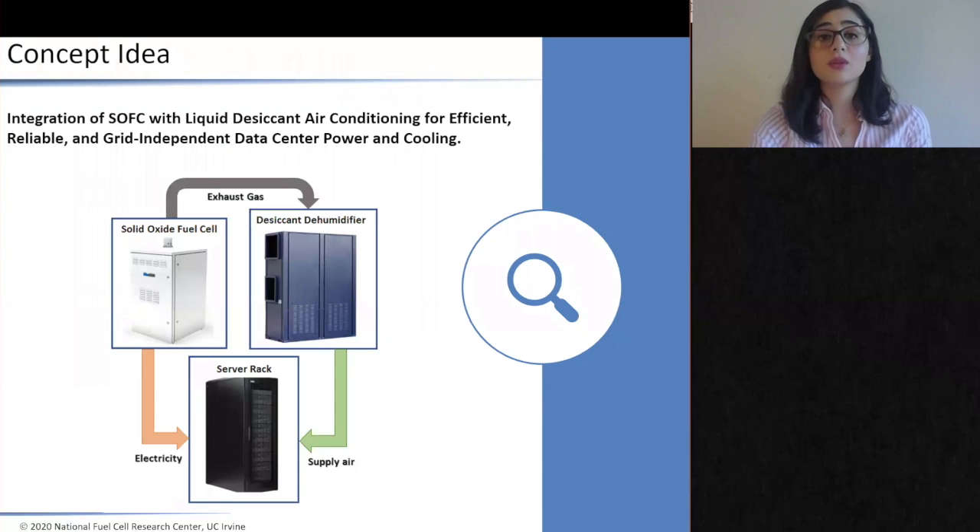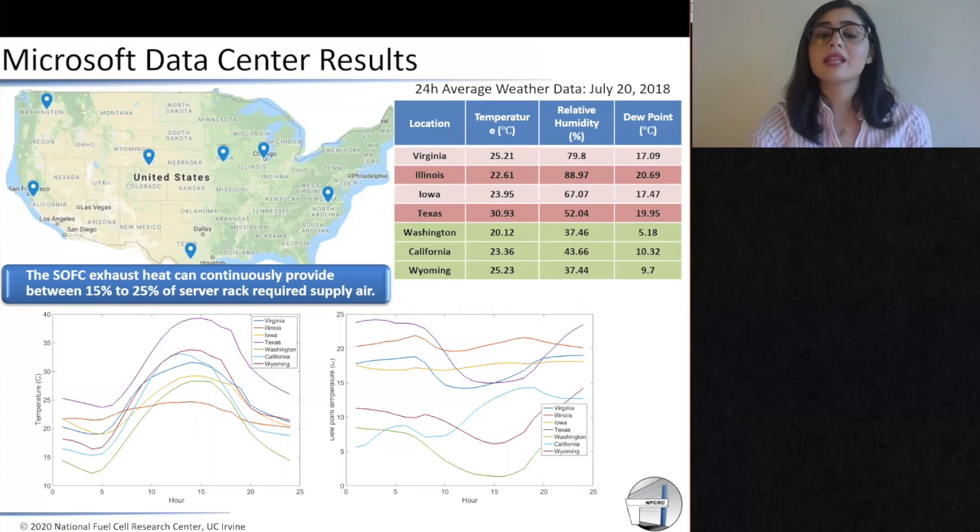That's why I introduced the idea of not only using one small-scale fuel cell for powering one single server rack, but using the exhaust of this single fuel cell for producing cold and humidified air in a desiccant dehumidifier to provide the cooling needed for that single server rack. I investigated this idea both theoretically and experimentally. Using my model to look at seven different locations where Microsoft has data centers in the United States, my results show that if we run our solid oxide fuel cell technology continuously and produce cooling, we are able to provide between 15% to 25% of the cold and humidified air needed for one single server rack.